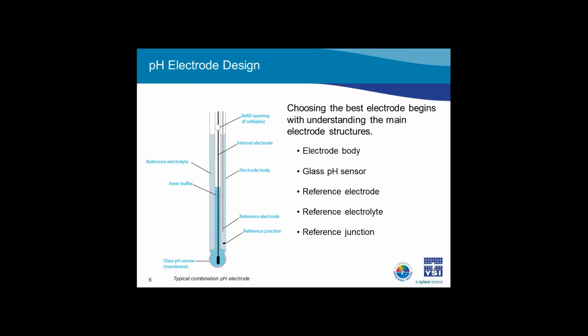A pH electrode consists of several structures, each of which can be seen in this figure of a typical combination electrode. The main components are the electrode body, the glass pH sensor, the reference electrode, the reference electrolyte, and the reference junction. It is important to understand these structures before choosing an electrode, as some structures can vary from electrode to electrode. Your application will determine the characteristics your electrode should have.